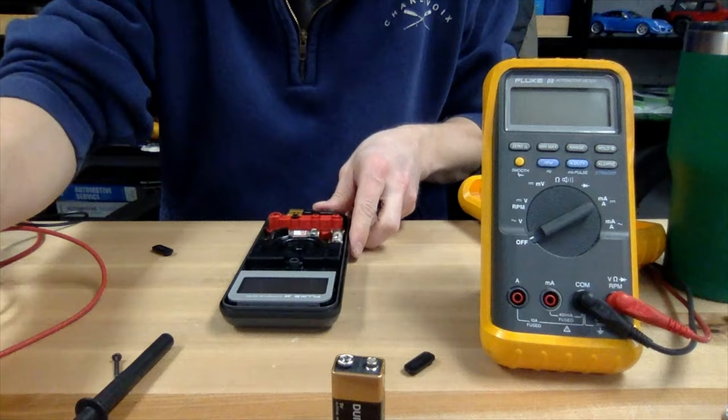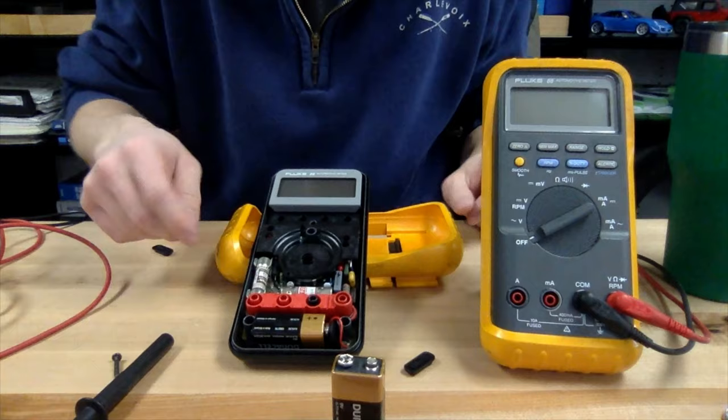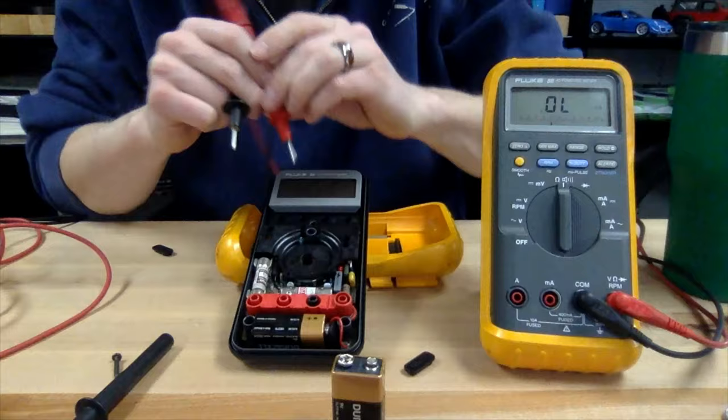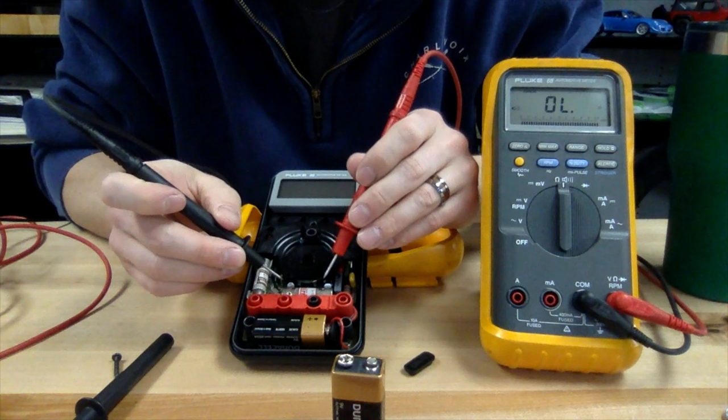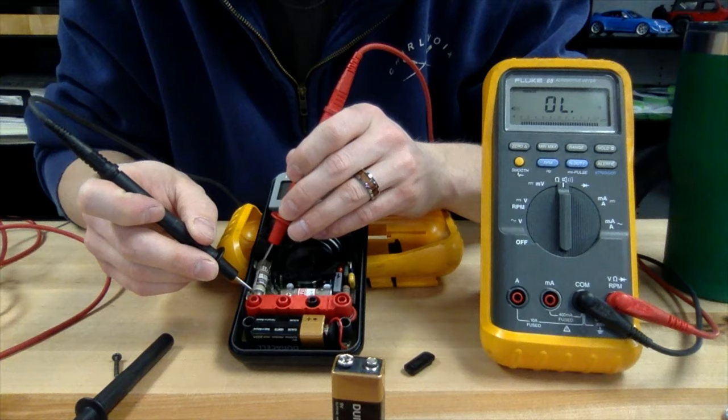If you look in the inside here, you'll see the two fuses, and we're going to set our known good multimeter to resistance and check these two fuses just like we did the test leads. It is important to note that the power is off on this meter. You never want to check resistance with the power on.